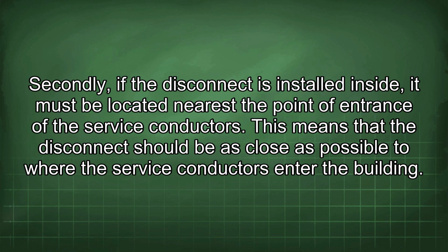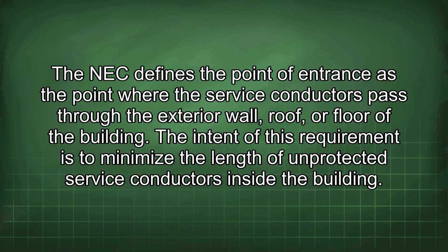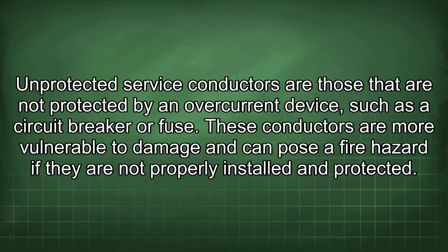Secondly, if the disconnect is installed inside, it must be located nearest the point of entrance of the service conductors. This means that the disconnect should be as close as possible to where the service conductors enter the building. The NEC defines the point of entrance as the point where the service conductors pass through the exterior wall, roof, or floor of the building. The intent of this requirement is to minimize the length of unprotected service conductors inside the building. Unprotected service conductors are those that are not protected by an overcurrent device, such as a circuit breaker or fuse. These conductors are more vulnerable to damage and can pose a fire hazard if they are not properly installed and protected.